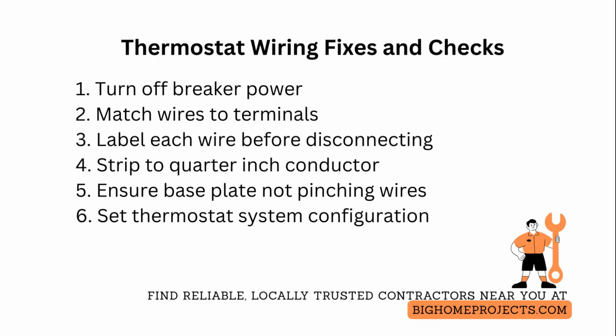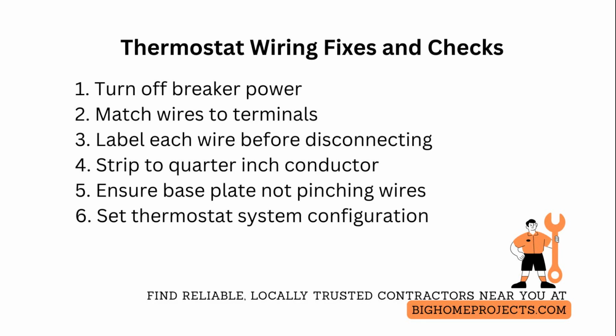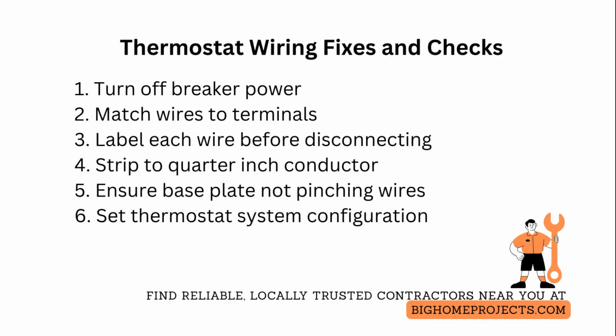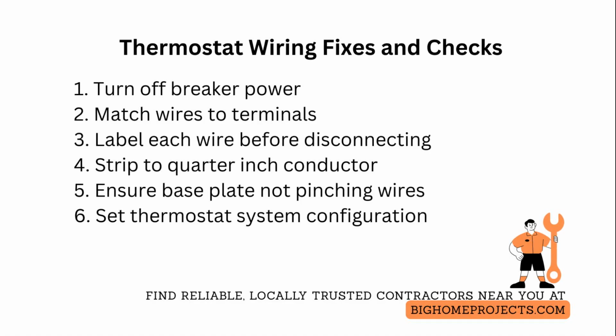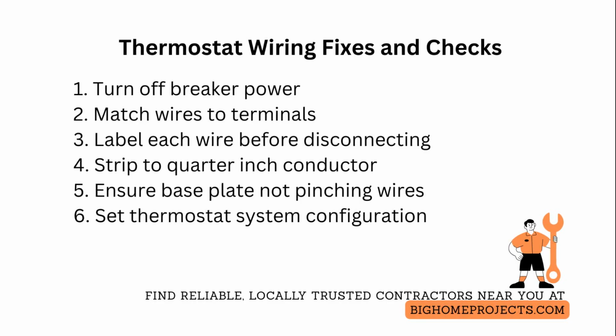wires are not shorted together and that the common or ground is not touching any live conductor. If you do not have the original thermostat photos, compare wire colors but trust terminal labels over colors because installers often reuse colors. Label each wire with tape as you disconnect so reassembly is exact. Check for exposed copper where insulation may have been stripped too far.